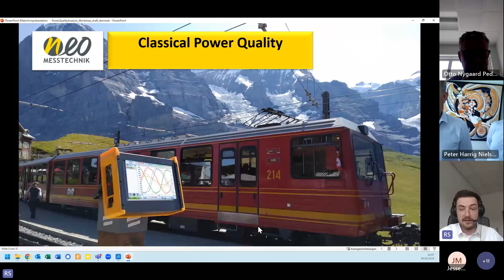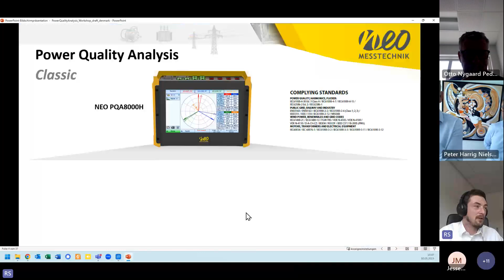And then we will start directly with the presentation. Let's talk about classic power quality analysis. We have heard already some introduction, but what do we actually mean by this? We talk about voltage quality, where we see dips, slow changes, fast changes, and voltage interruptions. We have long interruptions, flicker, swells, transient recording. We have harmonics, where we talk also about THD, and we see the standard classical report EN50160 with all the parameters, like frequency stability, harmonics, and harmonics evaluation, THD.